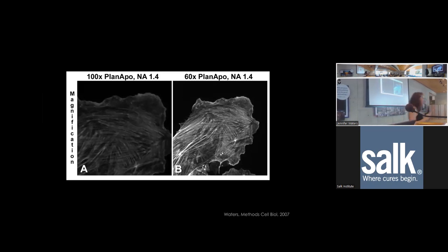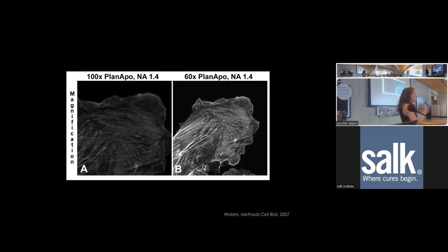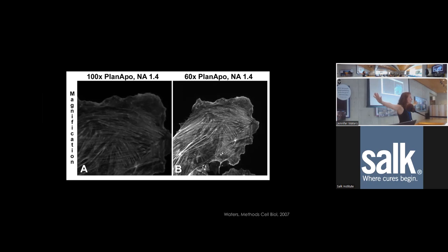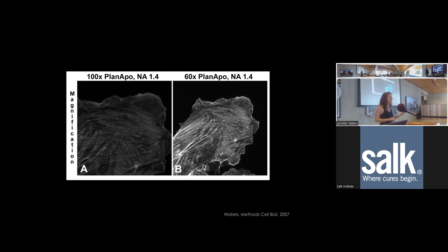Magnification also affects brightness. With the same numerical aperture, a lower magnification lens produces a brighter image because the light collected is spread over a smaller area on the detector, giving more photons per pixel. At higher magnification, that same amount of light is spread over more pixels. So use only as much magnification as you actually need to achieve good sampling.